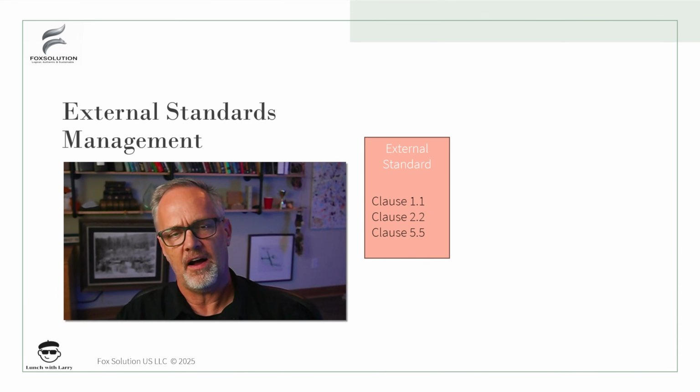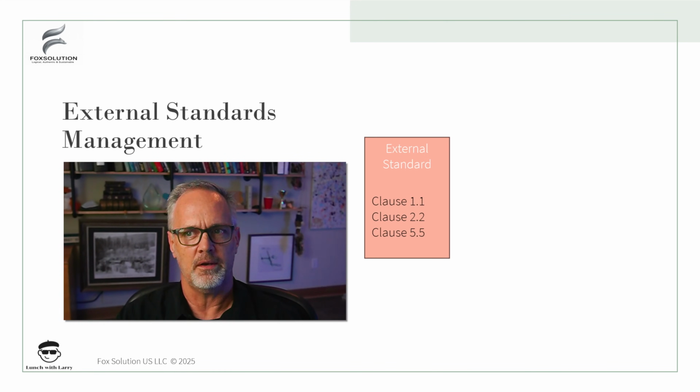Maybe 11135, which is ethylene oxide sterilization of medical devices, maybe 60601, electrical medical device requirements, ISO documents. There's also ASTM standards for testing. There's IEC, IEEE, right? All these different agencies that have committees that sit around and decide for a particular scope of work what requirements are necessary to assure that a device gives you the performance that it needs. And so in this case, we bring the external standard into the tool and we break it down by clause. So each one of the clauses defines some aspect of how the device should be developed.